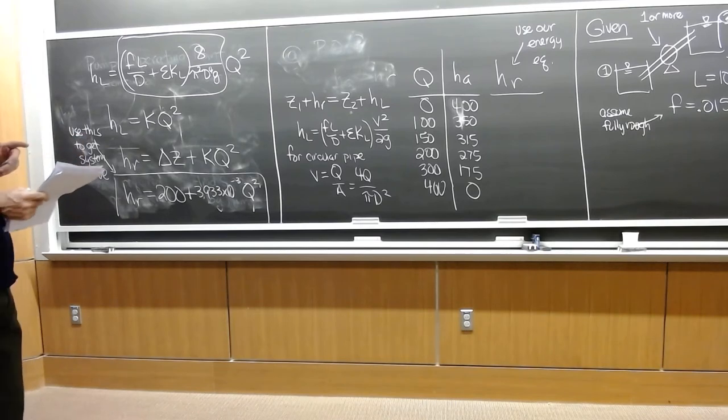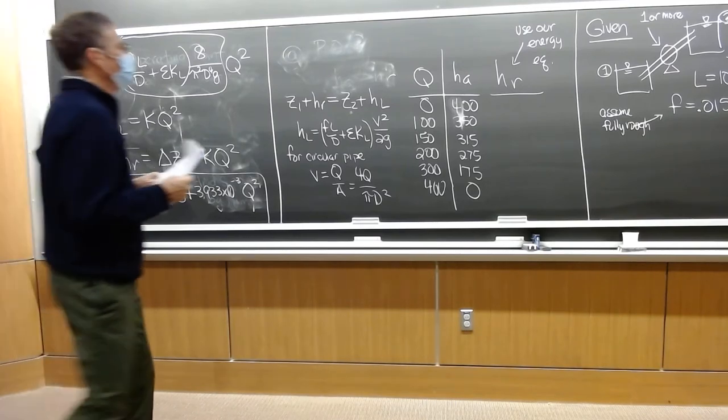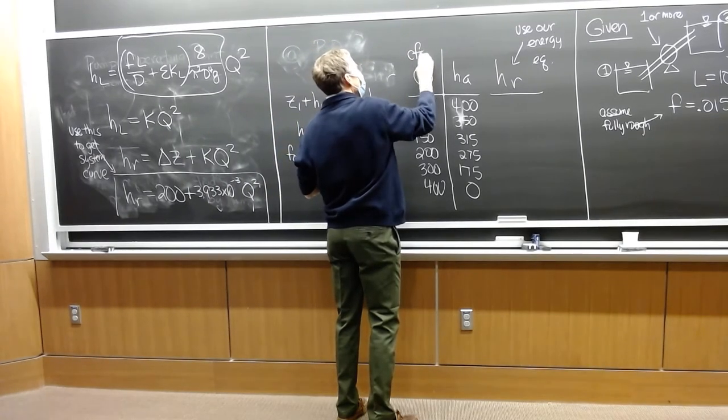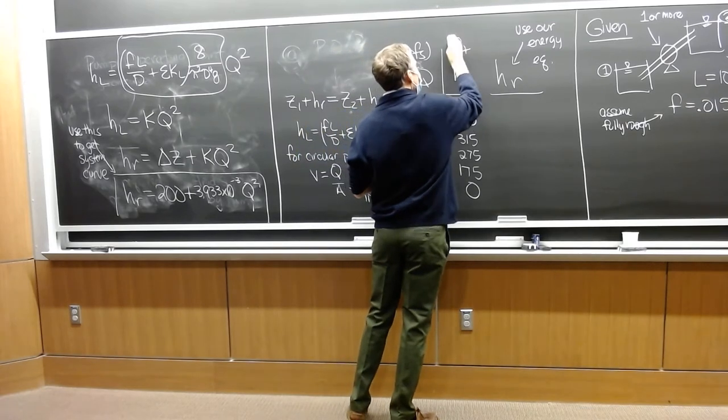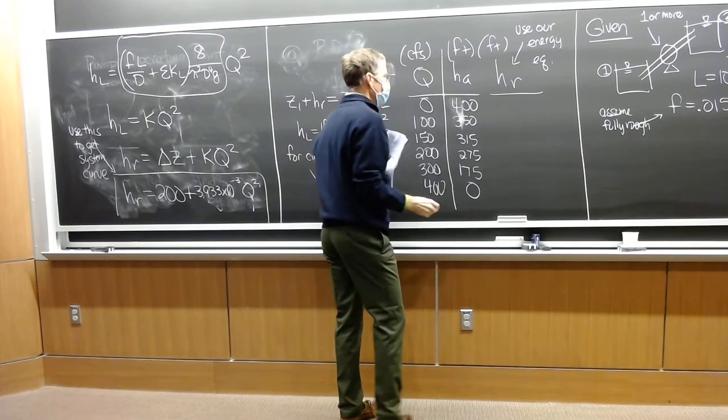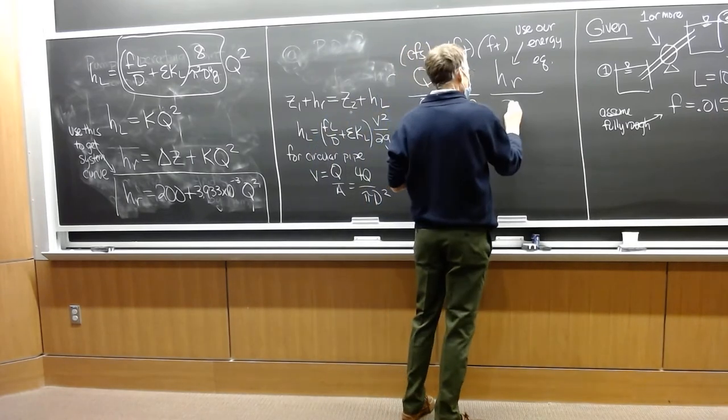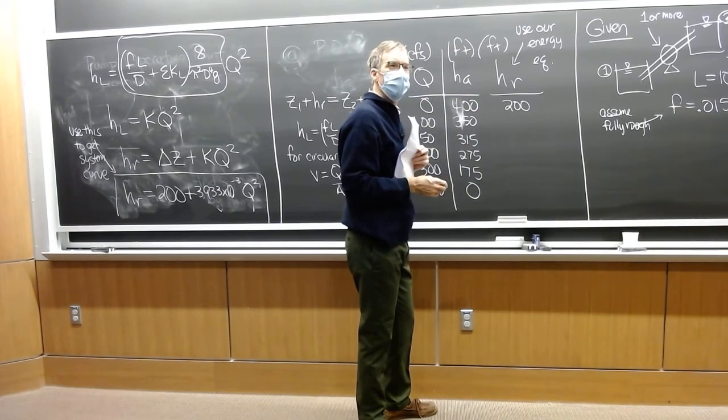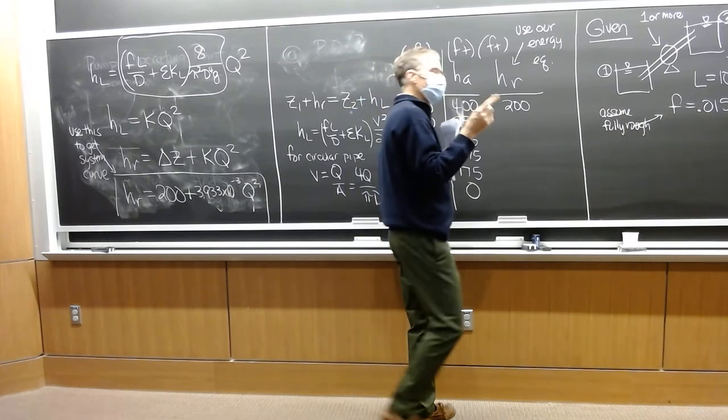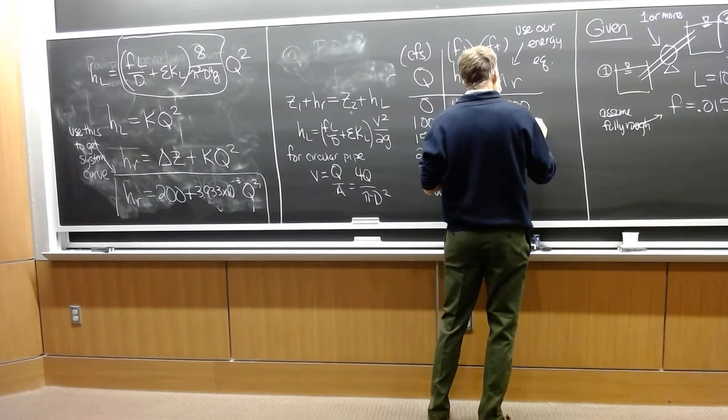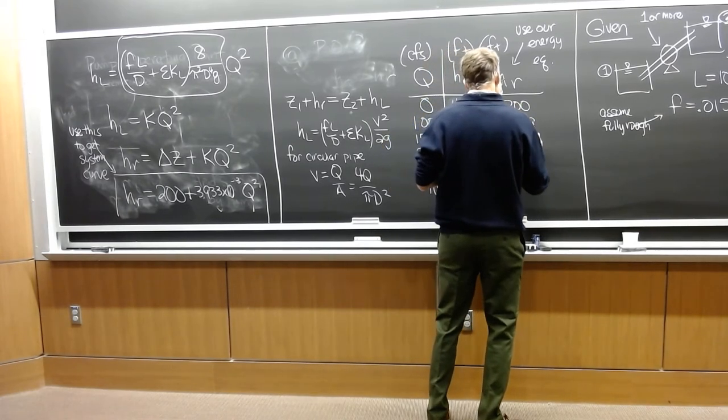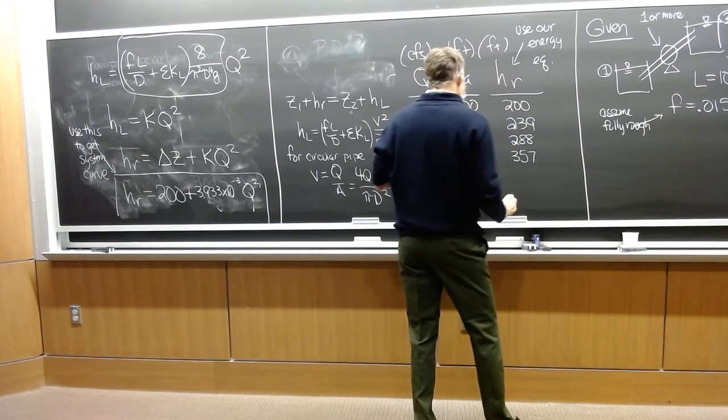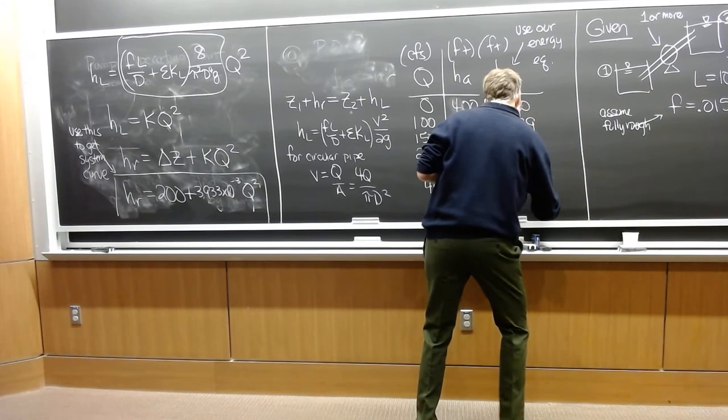And I calculated the head required at the various Q's. That's 200 feet at zero flow, then it goes upward from there: 239, 288, 357, 554, 829. It has the look that we expect it to have is that it starts at a non-zero value. And then as we add flow, we're adding more head required.